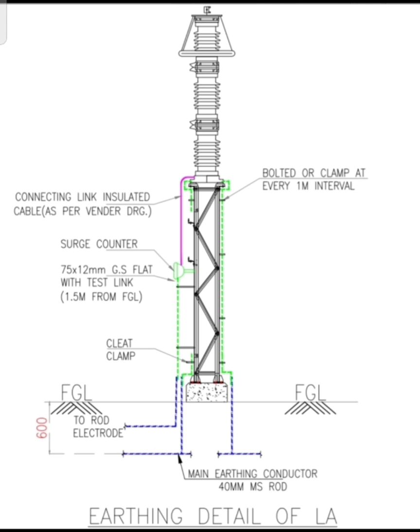You can refer to any of the four documents I have mentioned: IS 3043, IEEE 80, CEA Regulation, Safety & Electric Supply Regulation 2010, and CBIP Manual 339 for more reference. I hope this clears all the doubts about the earthing of lightning arrestors or surge arrestors. Thank you everyone for your support.